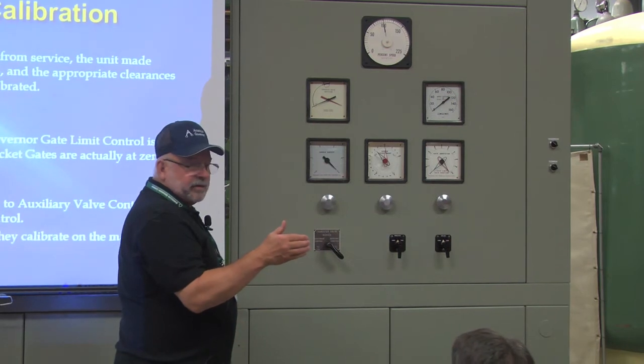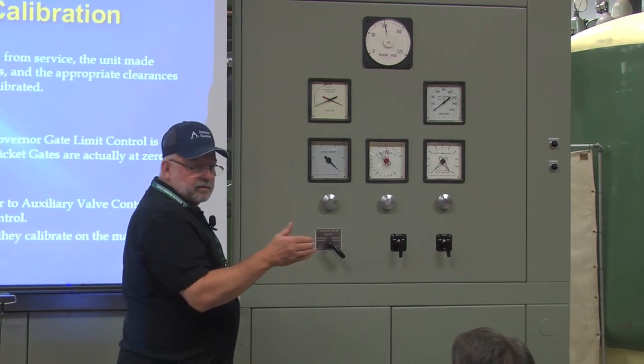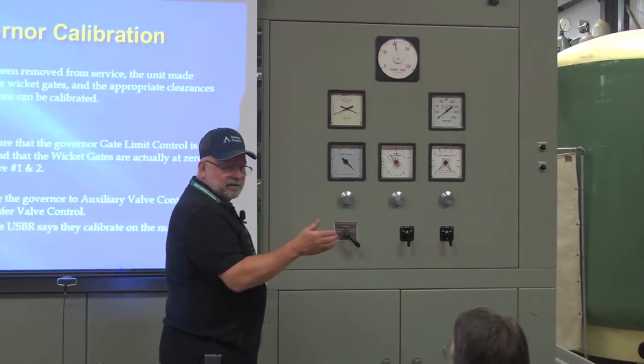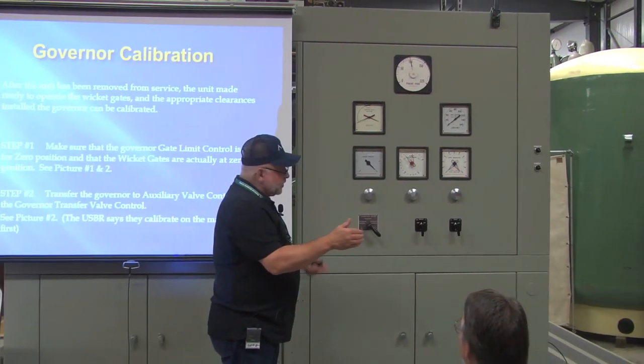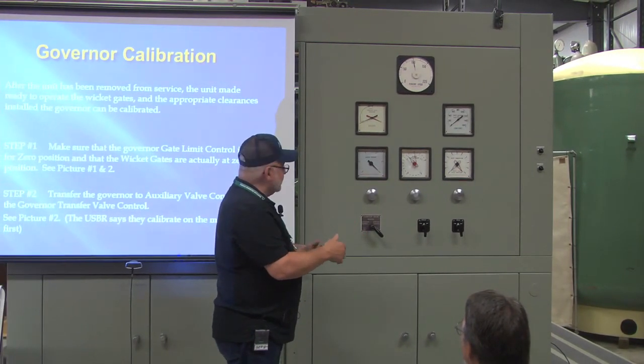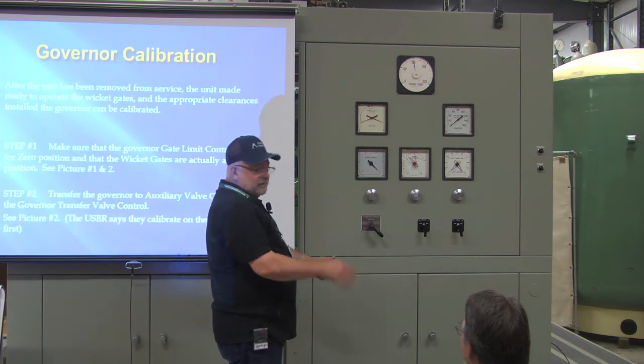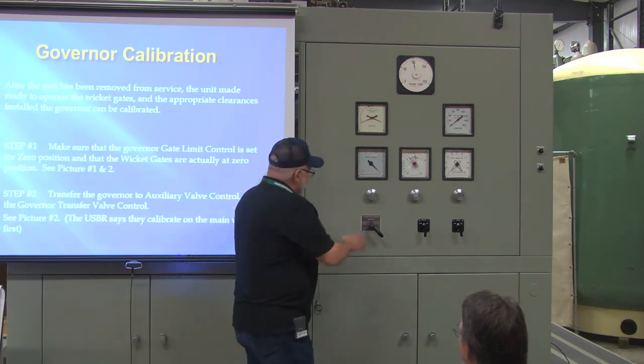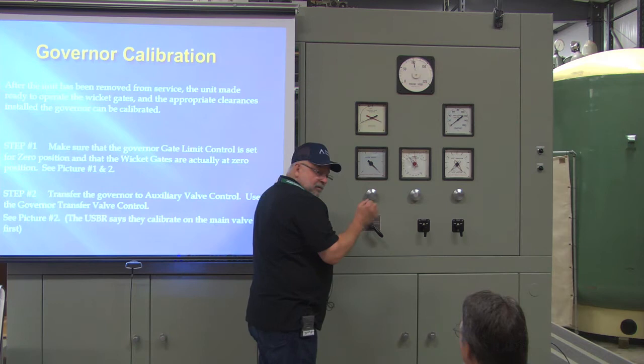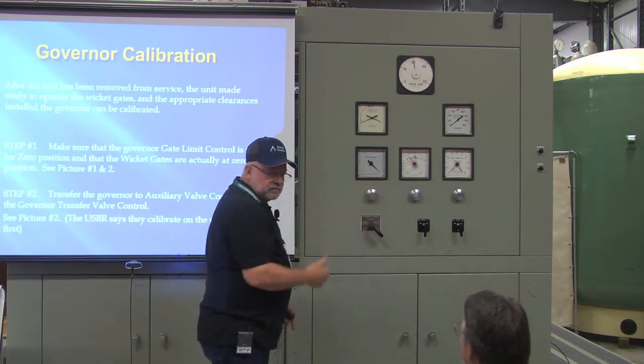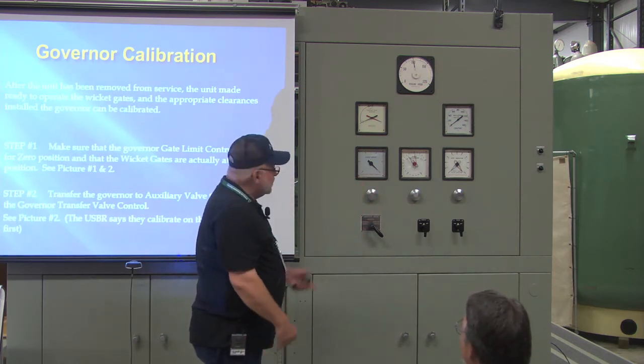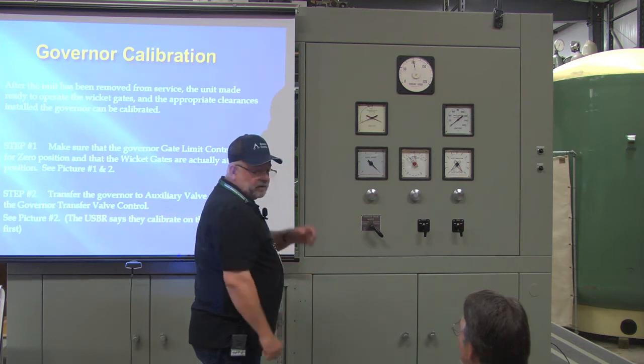Well, the deflectors just stay right where they are in auxiliary valve. They don't care about deflectors. Those are for upsets and shutdowns, all right? So they're just out to the side. So when I got down there was a guy kind of in front of the governor cabinet, and I reached around him, and I just touched that, and boom, I could hear the deflectors come in, and it started to stop that water.